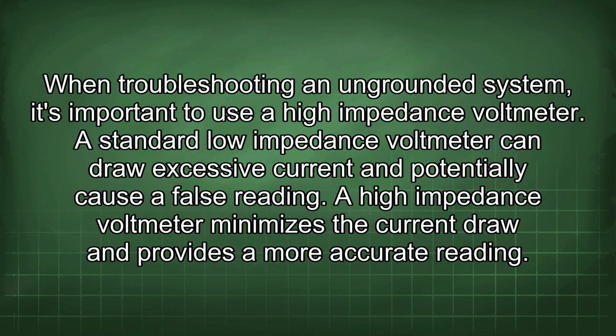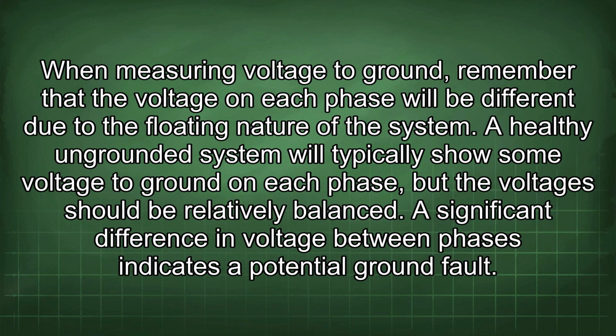When troubleshooting an ungrounded system, it's important to use a high impedance voltmeter. A standard low impedance voltmeter can draw excessive current and potentially cause a false reading. A high impedance voltmeter minimizes the current draw and provides a more accurate reading. When measuring voltage to ground, remember that the voltage on each phase will be different due to the floating nature of the system. A healthy ungrounded system will typically show some voltage to ground on each phase, but the voltages should be relatively balanced. A significant difference in voltage between phases indicates a potential ground fault.